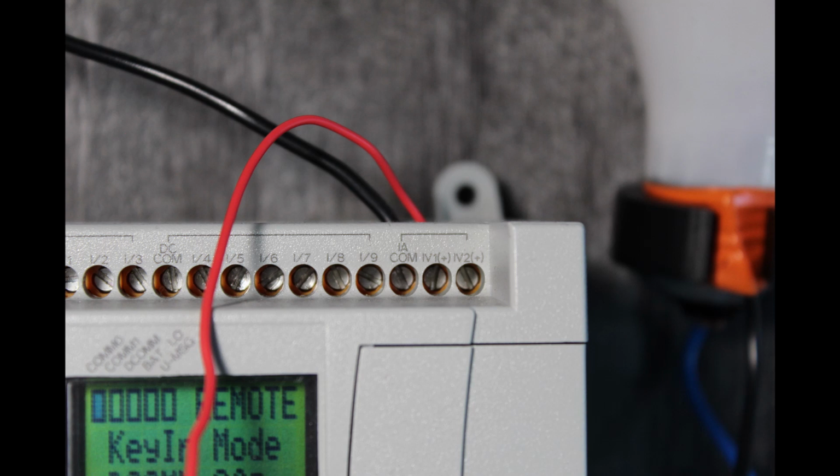Before we jump into RSLogix, I just wanted to quickly show how I've got it wired up, or how it would look. The red wire is going to be the signal wire, the output wire off my sensor, and that is landing on IV1, which is my analog input 0. And then you can see also that both these analog inputs have a common, which is the black wire that needs to go back to your negative or your ground.